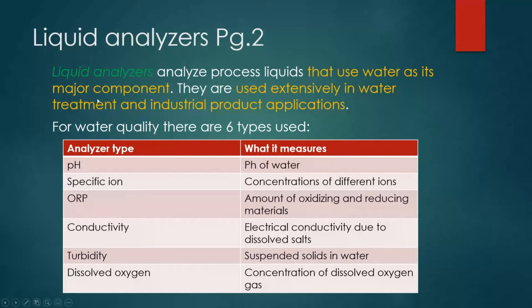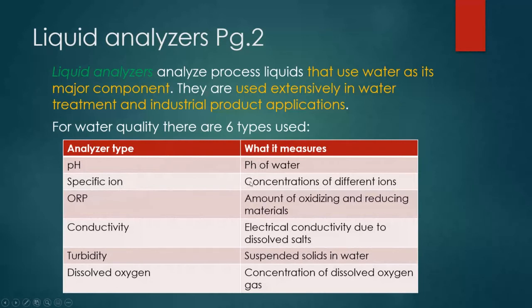When analyzing for water quality, we use six different types of analyzers, and these are the six types covered in the three ILMs for liquid analyzers. We have pH, which measures the acidity or alkalinity of water. We have specific ion analyzers, which are designed to measure specific types of ions. A common example in drinking water is fluoride — we add fluoride to our drinking water, so we would have a fluoride-specific ion analyzer to measure its concentration.